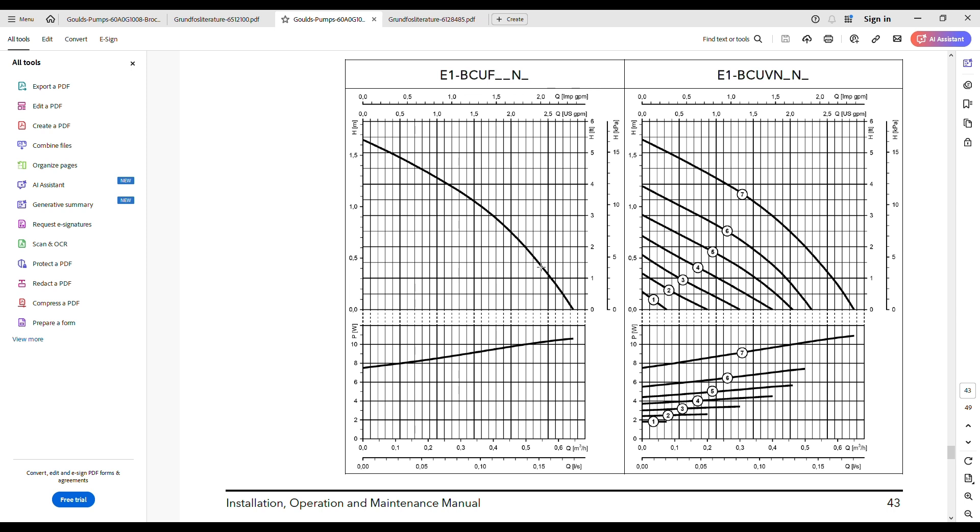I think that the head pressure, the back pressure of trying to move the water through the outlet and into the hot water tank, was not enough to restrict the flow. So what the valve does is, as you close the valve, it moves, I hope you can see my cursor here, as you close the valve it builds the pressure up. So the flow reduces.